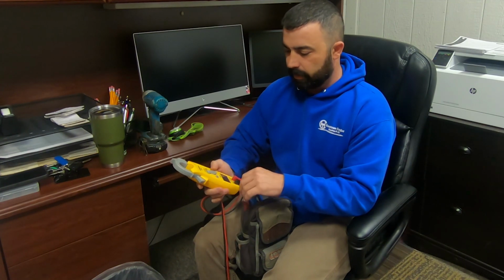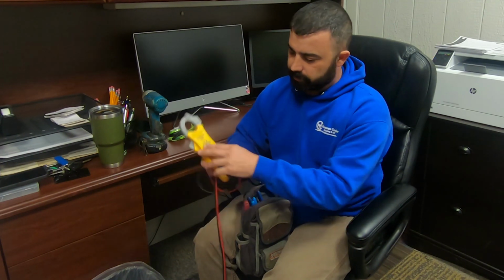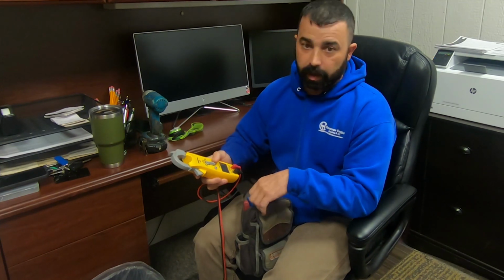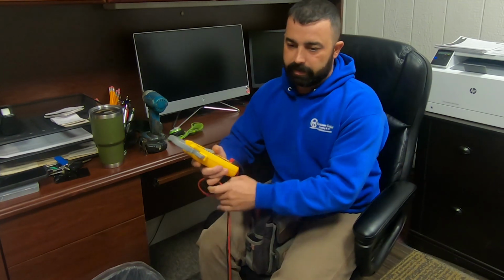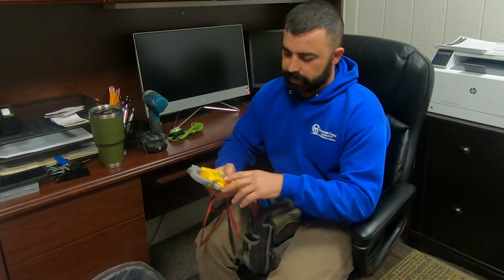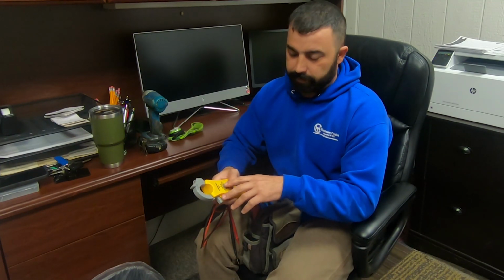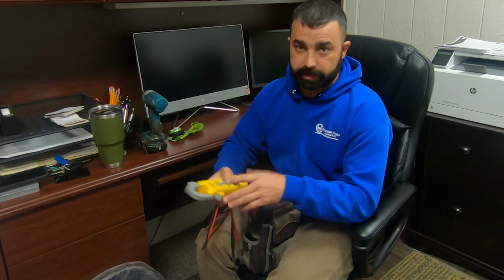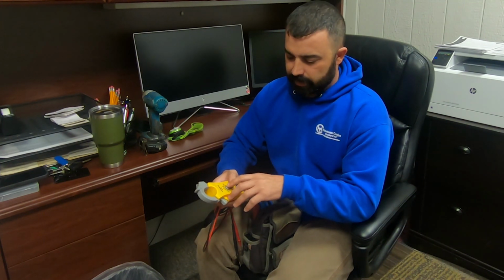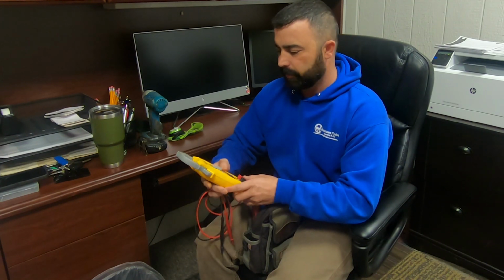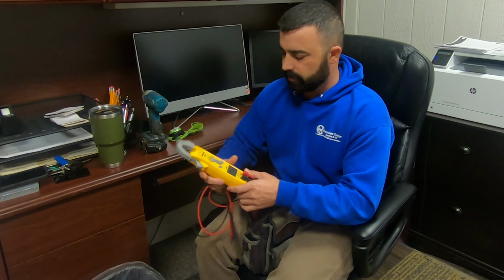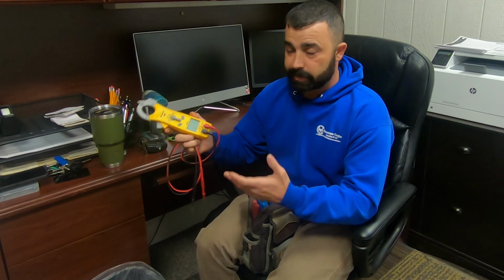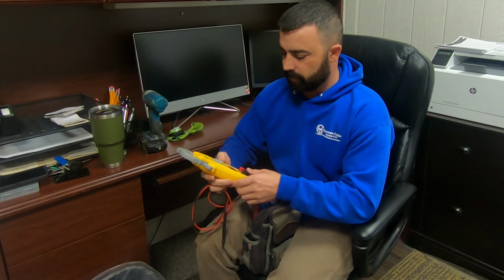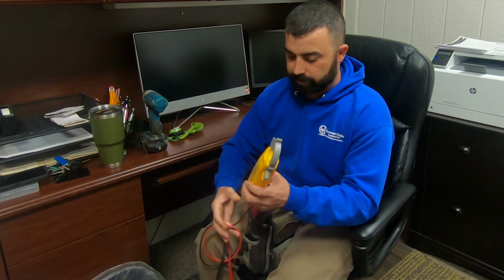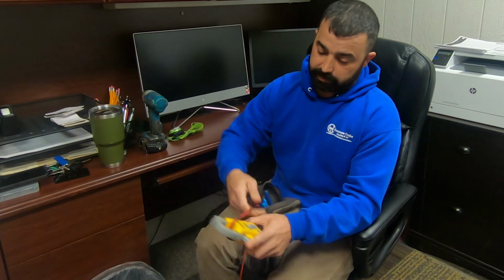You want to be able to check your capacitors. That's what the microfarad reading there is. You want to do ohms. Check for ground on the different things, check relays and whatnot. Of course, your voltage, AC amps and voltage, volts DC, and millivolts DC for checking flame sensors. That's the meter I use. It seems to do just about everything I need. It's relatively inexpensive compared to some of the other meters, but I've had it for several years and it's giving me no issues.